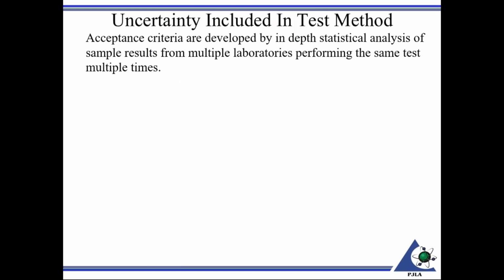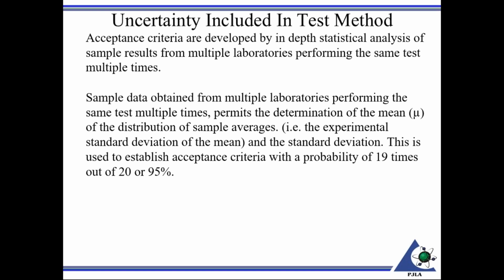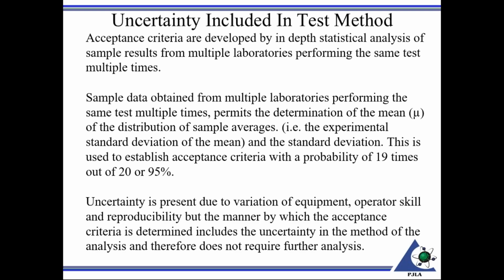Again, the acceptance criteria are developed by in-depth statistical analysis of samples from multiple laboratories performing the same test. Sample data obtained from multiple laboratories performing the same test permits the determination of the mean of the distribution of the sample averages, i.e. the experimental standard deviation of the mean, and the standard deviation. This is used to establish acceptance criteria with a probability of 19 times out of 20, or 95%. Uncertainty is present due to variation in equipment, operator skill, and reproducibility, but the manner by which the acceptance criteria are determined includes the uncertainty in the method of analysis and therefore does not require further analysis.